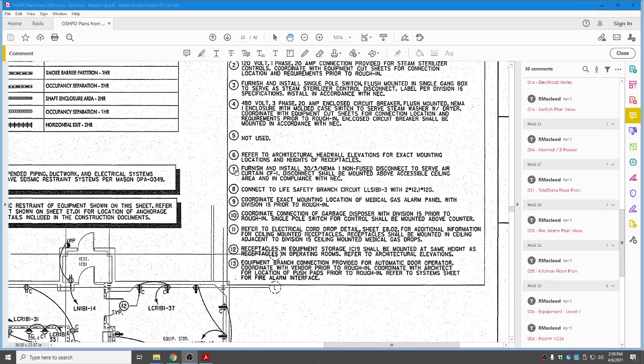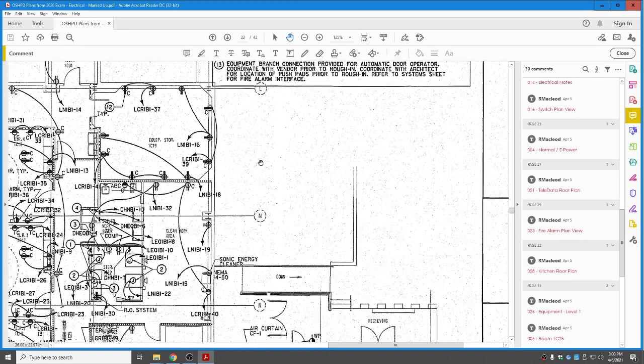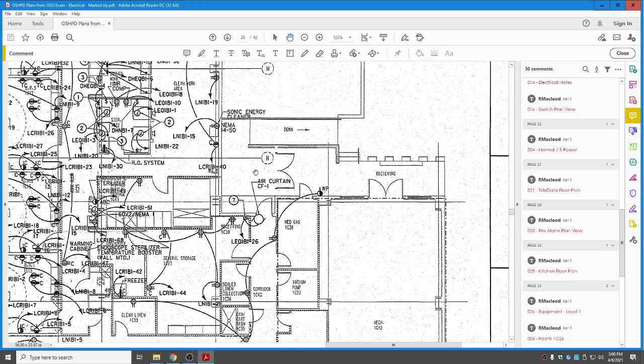Well, let's call that first off the CEC. And also, what has to happen to make this accessible in the above ceiling space? We need to have equipment space up there in front of the disconnect that has some width to it and some distance in front of the non-fused disconnect switch for service and maintenance. Let's drop down and show you that circle 7. There's our air curtain in the center, CF1, and there's the circle 7 to the non-fused disconnect.